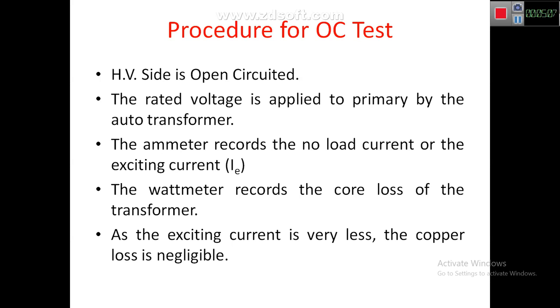In this test we do not get any output — all power supplied is lost. The total power loss is divided into core loss and copper loss. Since the current is very small in the OC test, copper loss can be neglected. Therefore, all the power measured by the wattmeter represents only the core loss.